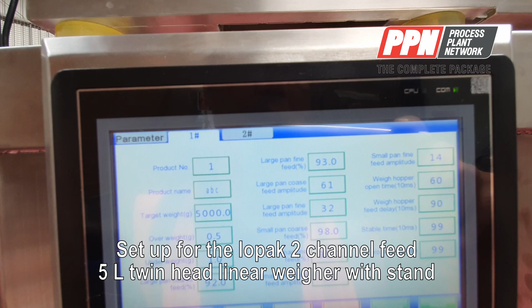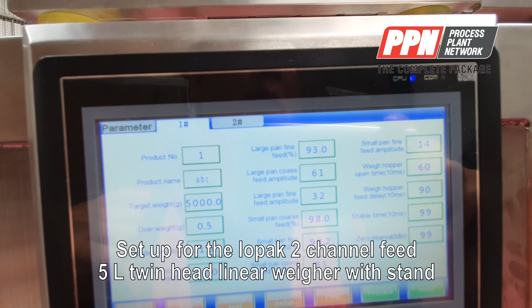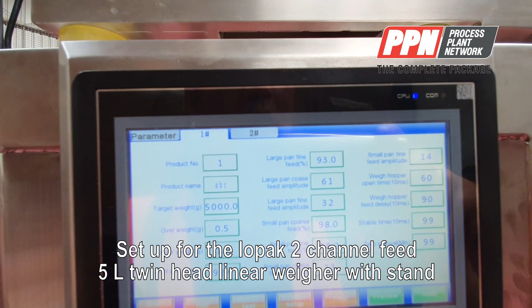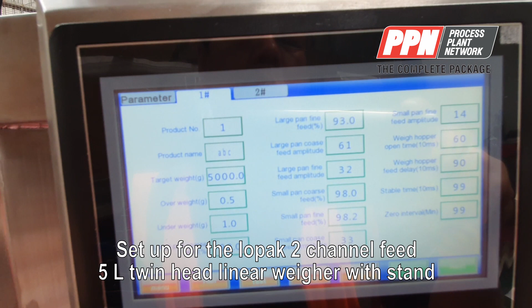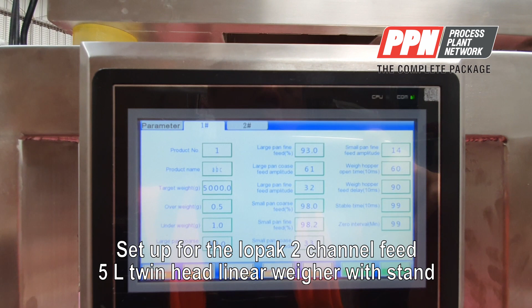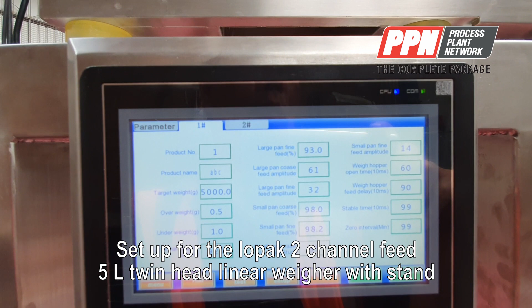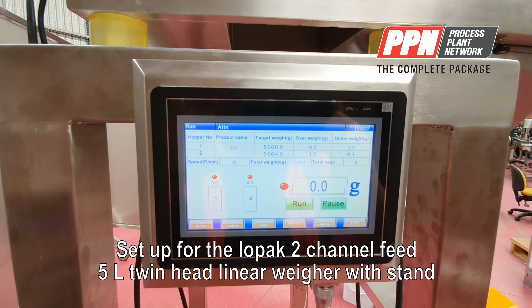If you have a bouncing product, let's say a ball bearing, it will bounce and take longer to become stable in the bucket. The larger the number, the more accurate you are, but that also slows down the system. Zero interval, in this case, we set it to 99 - meaning after 99 dumps, the bucket will ultimately do a zeroing.